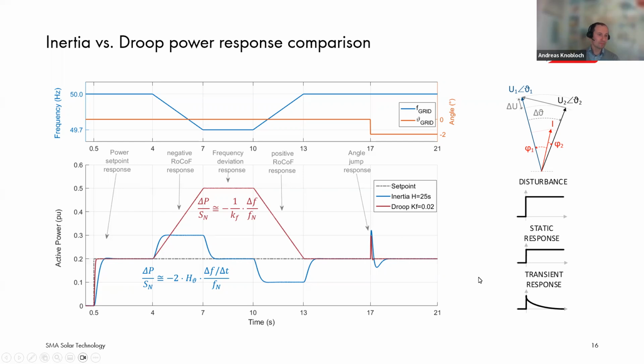response behavior. So there are, let's say, multiple ways how our inverter can respond to grid events of a different type. Yeah, there is an infinite number of trajectories that we can choose to achieve a final state that is also to be defined. And we provide with our control two of them. And these two control modes are characteristic in the way that they provide a response to the frequency deviations. As you see here, in case of a droop control mode, the resulting power response is proportional to the frequency deviation from a frequency reference value. In that case, it could be 50 Hertz.